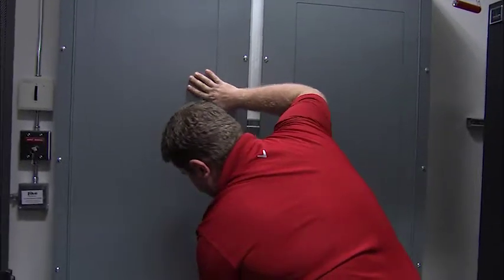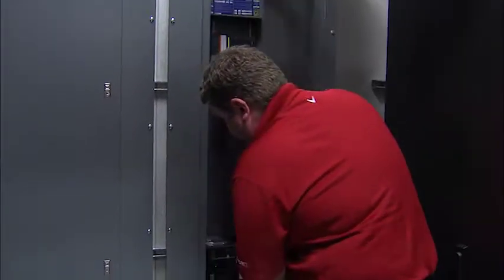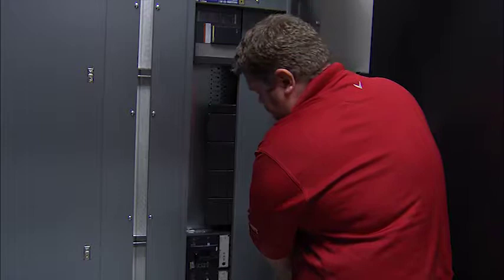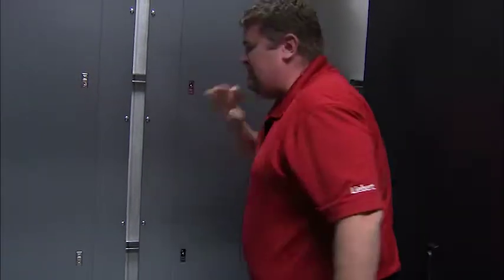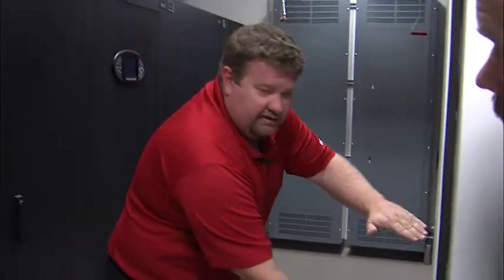And it's identical in this one. Kill the inputs of these and pull them out completely and replace them. So if only one system went down, so let's say in 20 years we come to end of life, 25 years end of life of the UPS system, technology changes, you guys understand that, and we want to pull these out. In 20 years they're probably going to be about this big. We can do that without ever taking down the load, essentially. That's the other thing, other than an emergency, why we put the wraparound system in.